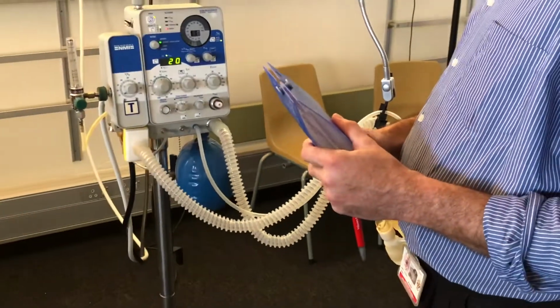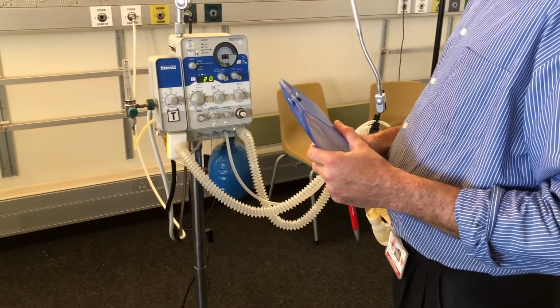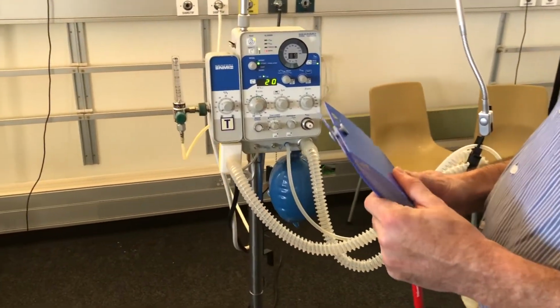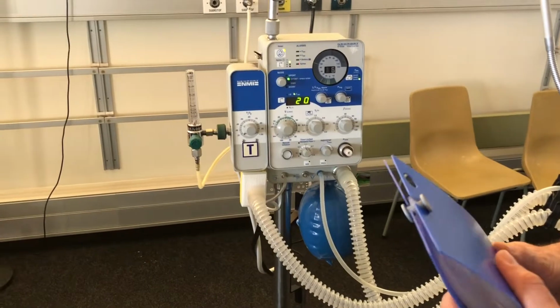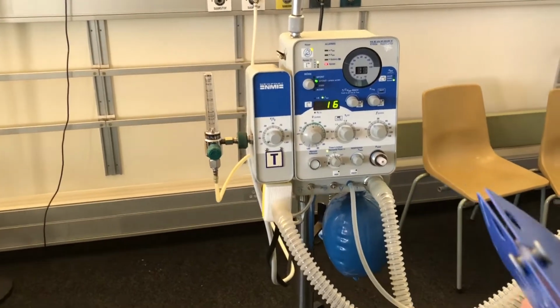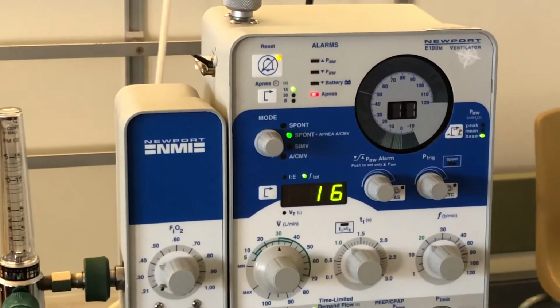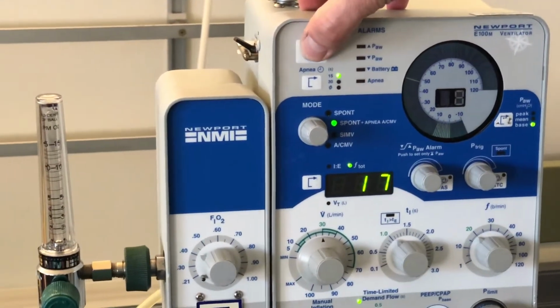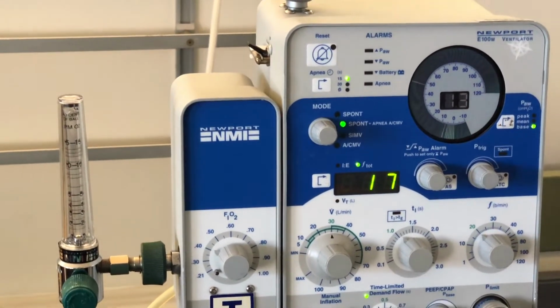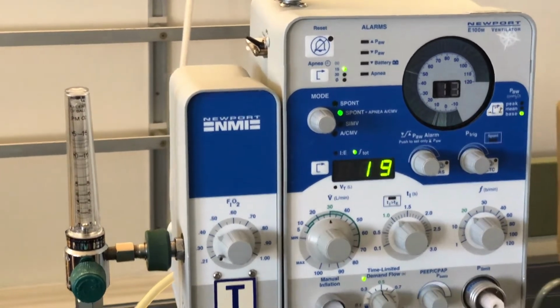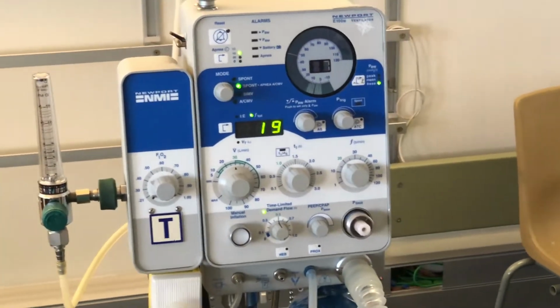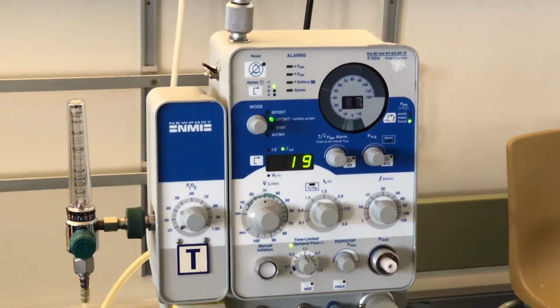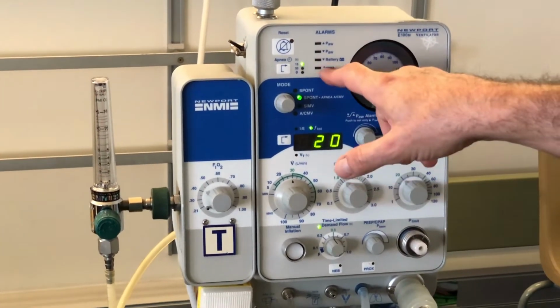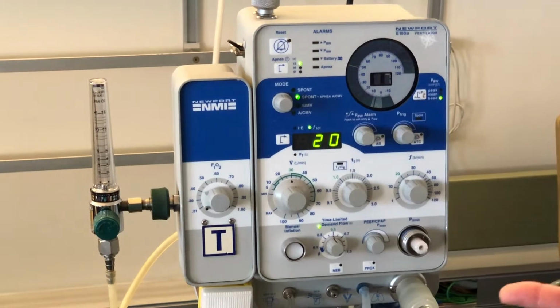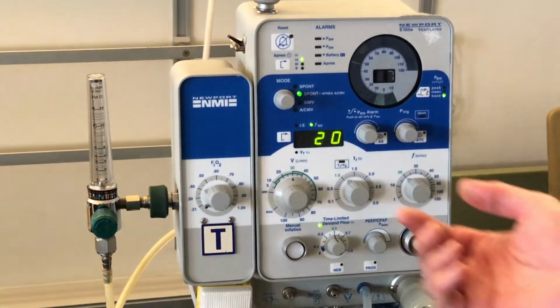So I'm going to try and make the machine detect triggers. And once the machine has satisfied itself that it's detecting regular triggers from the patient, the apnea light will stop flashing and will become a solid light, as you see there. Once the solid light is on, I can clear the alarm, and if the patient continues to breathe spontaneously, the machine will be satisfied. Again, if the patient stops breathing now, after 15 seconds, the apnea light will start to flash and the machine will commence with its backup ventilation.